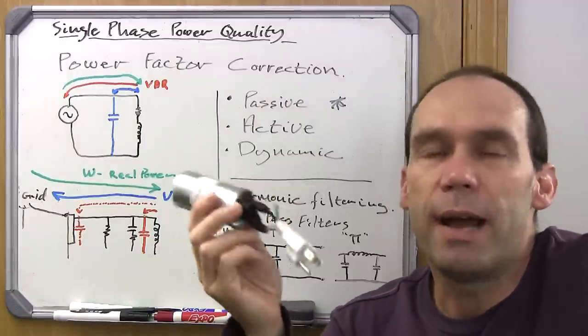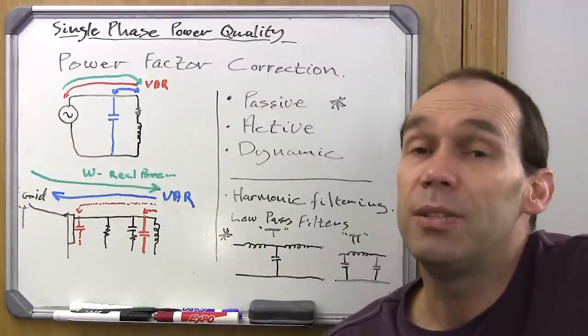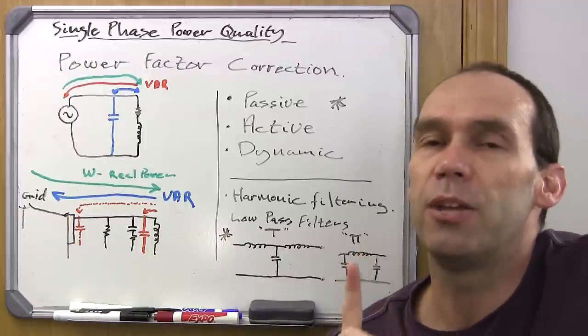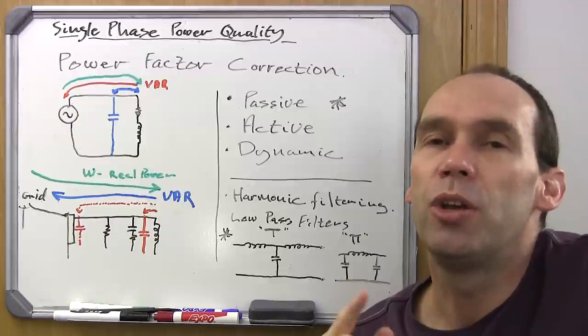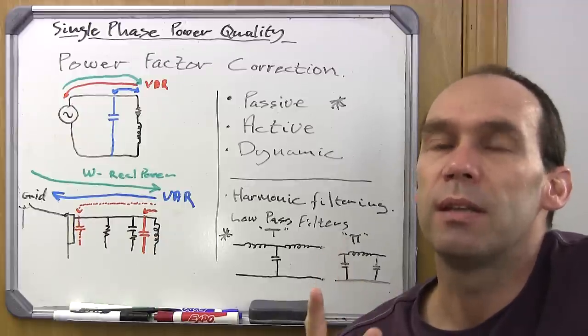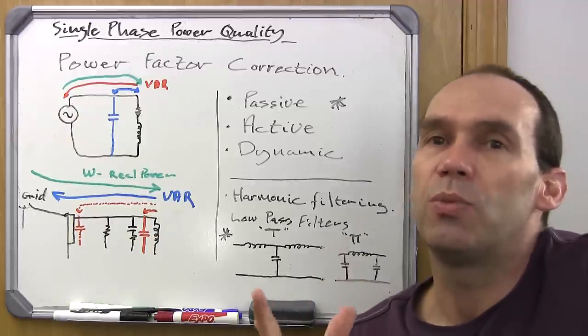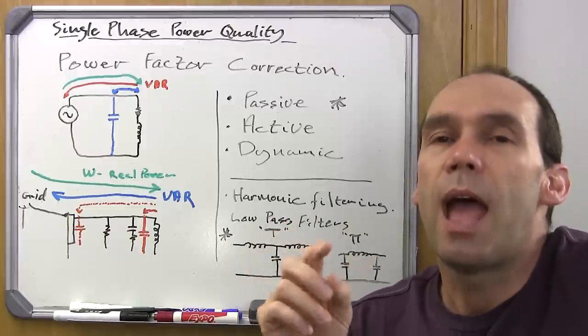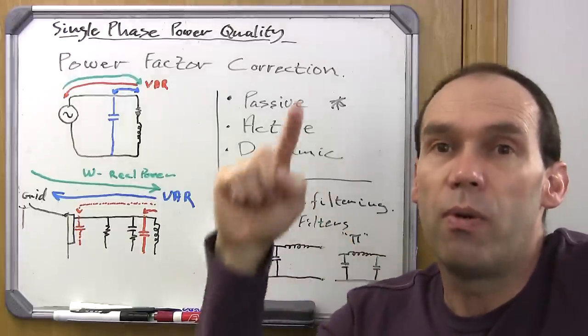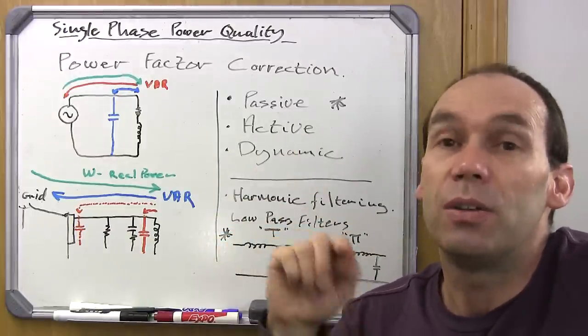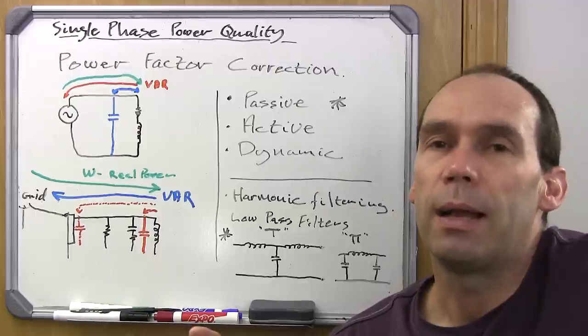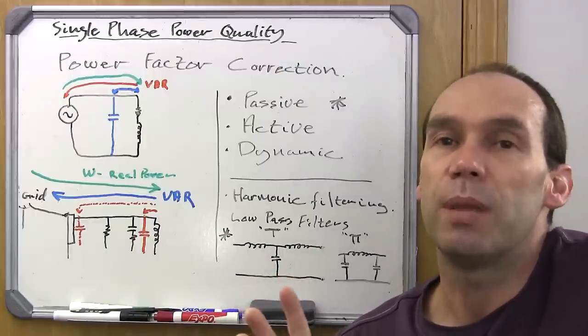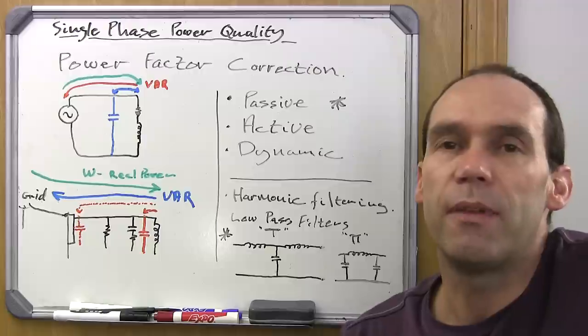There's also the issue of resonance. By plugging inductors or capacitors into an AC circuit without proper forethought — especially if there are harmonics you're not addressing — you can create resonance. Resonance can lead to a situation where the impedance of a circuit changes radically, potentially causing over-voltage that can damage equipment on that power line. So again, it's a fine art and not something you want to just play around with.